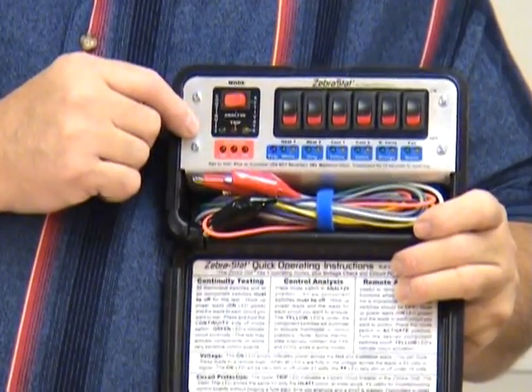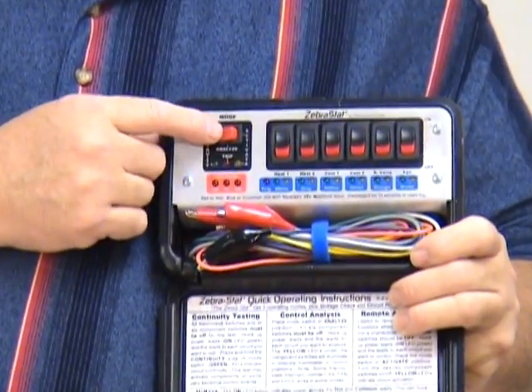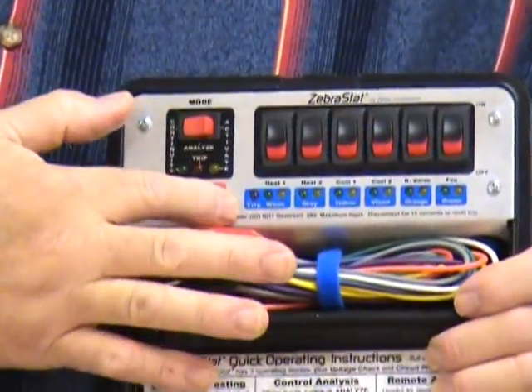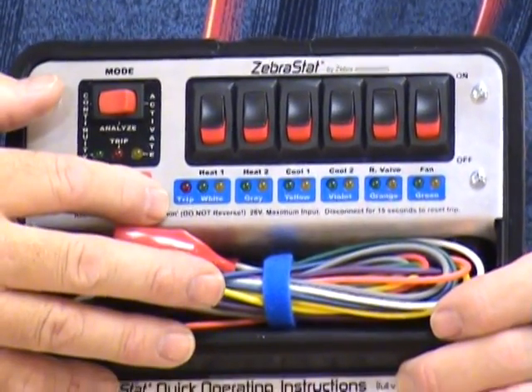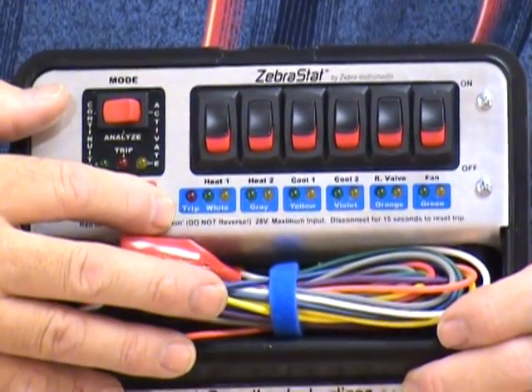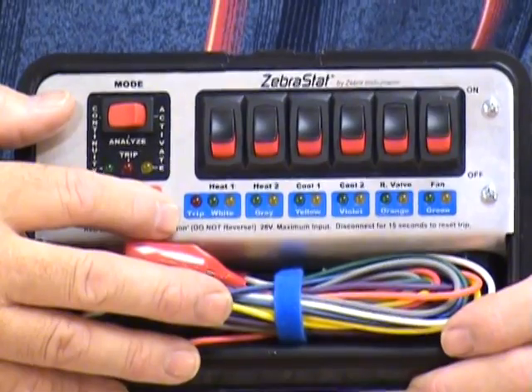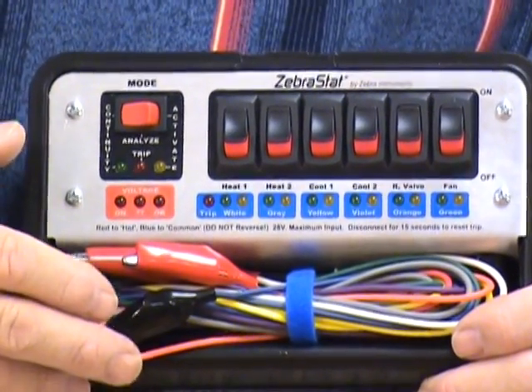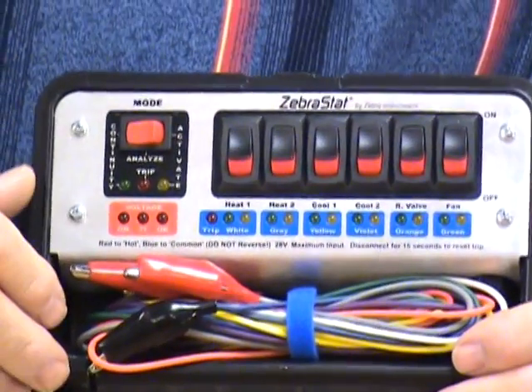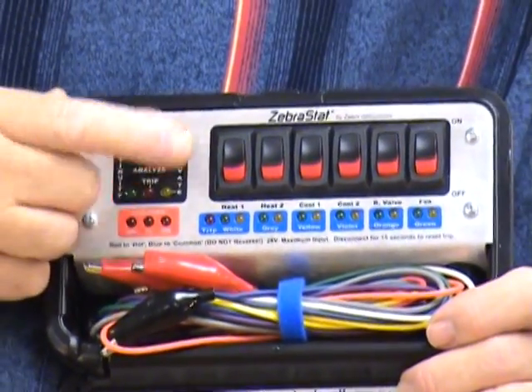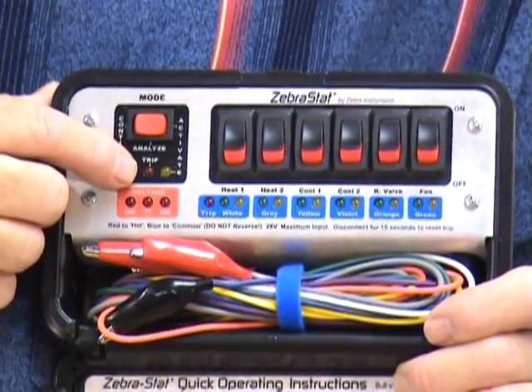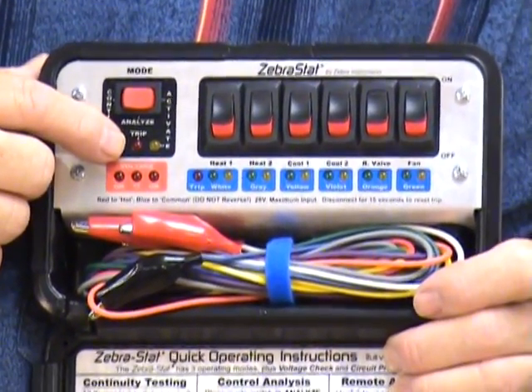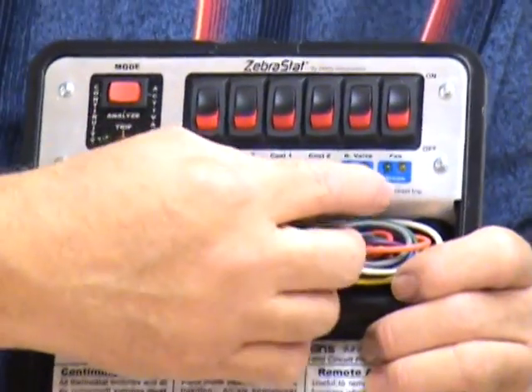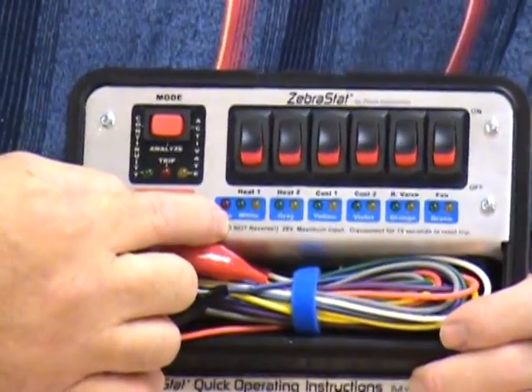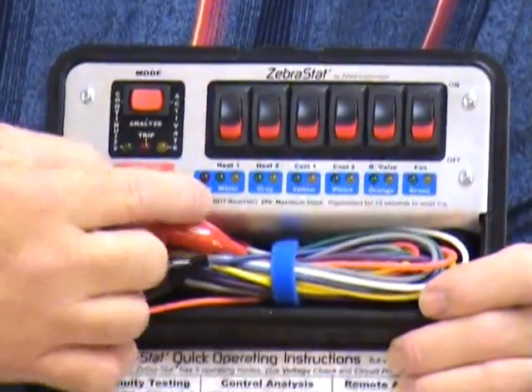It also has a continuity checker. When you put this switch in this position, it does 6 simultaneous continuity checks to make sure that you at least have an electrical path going to those devices that are downstream of your thermostat wires. The middle position is simply a monitoring position if you're using a thermostat or other device to control it. And with the yellow lights down here, you can see what's active and what's not.